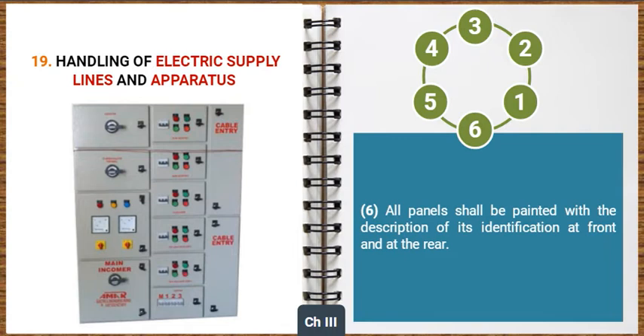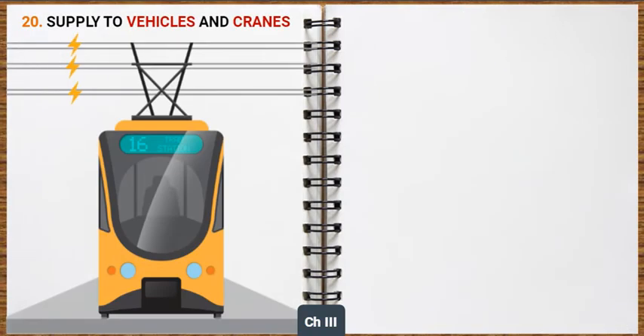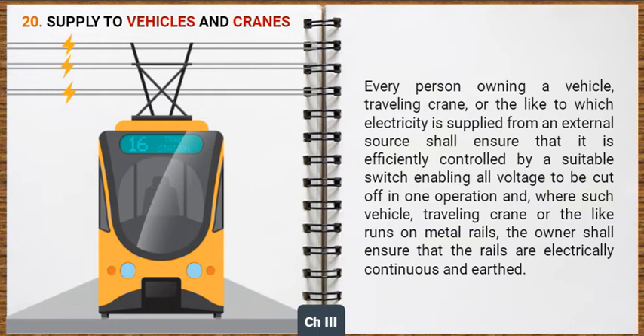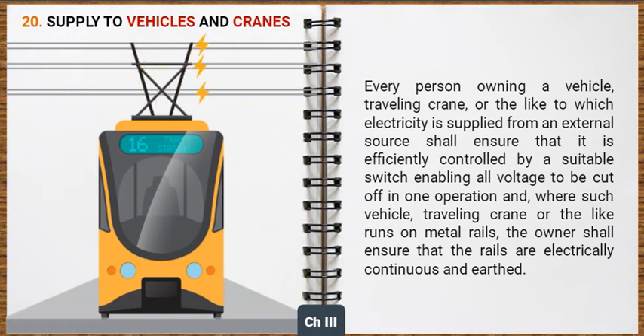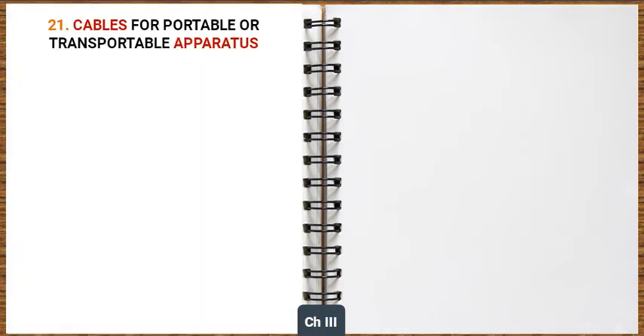Now let's look at the general safety requirements for supply to vehicles and cranes. Every person owning a vehicle, travelling crane or the like to which electricity is supplied from an external source shall ensure that it is efficiently controlled by a suitable switch enabling all voltage to be cut off in one operation. Where such vehicle, travelling crane or the like runs on metal rails, the owner shall ensure that the rails are electrically continuous and earthed.